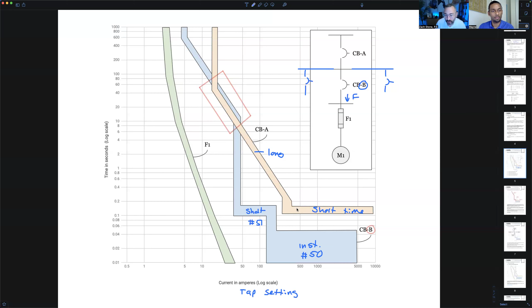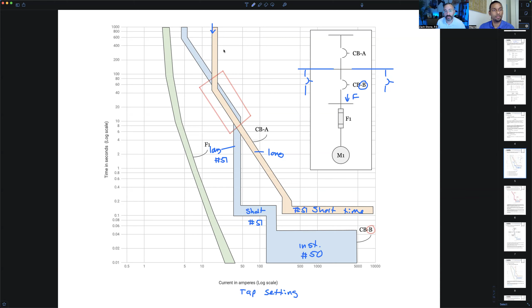So you've got a couple of different segments of these curves, right? We can adjust the tap setting. We can adjust the time delay for the ANSI 51s. And we can also adjust the curve type, make them more or less inverse, but that's not part of the answer choices. The key to realize is that when I adjust the tap setting, I'm only adjusting the tap setting of one portion of the curve. So for example, this would be the tap setting for the long time trip region for circuit breaker A. This value right here, that leading edge. If I can move this vertical portion to the right, I could potentially get it out of the overlap with blue.